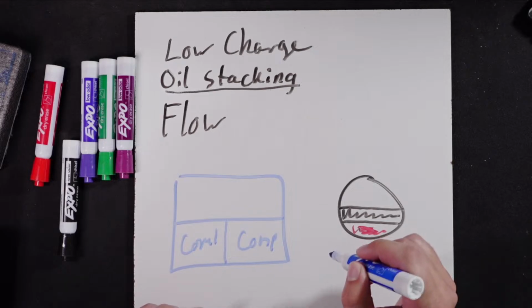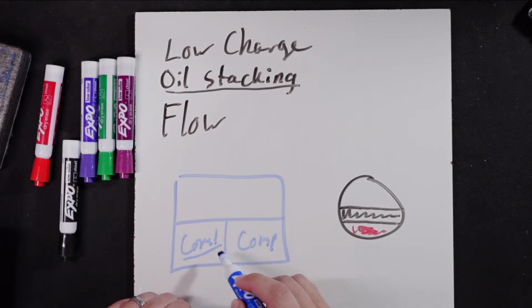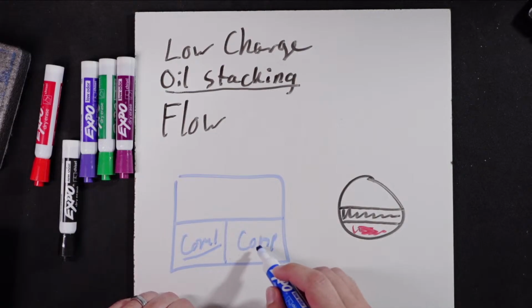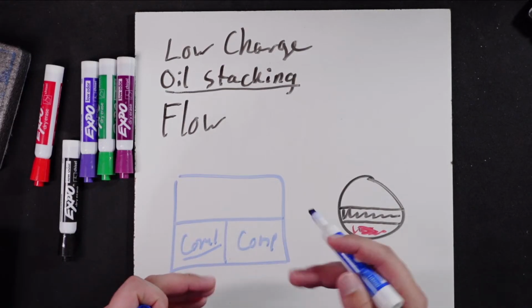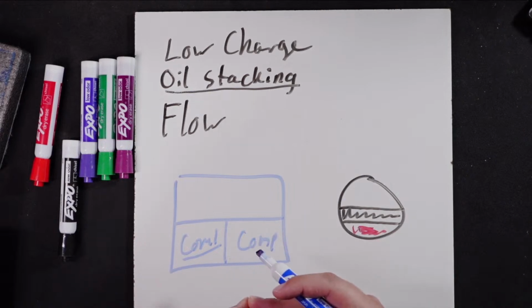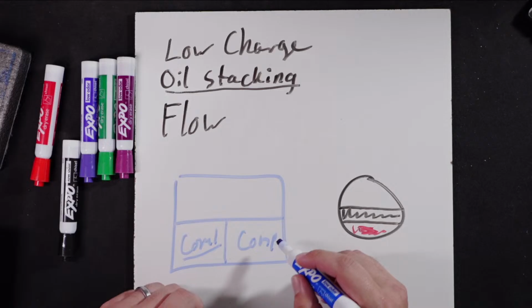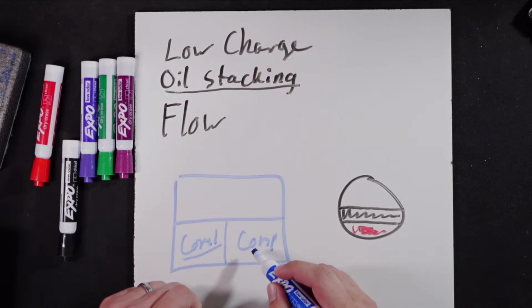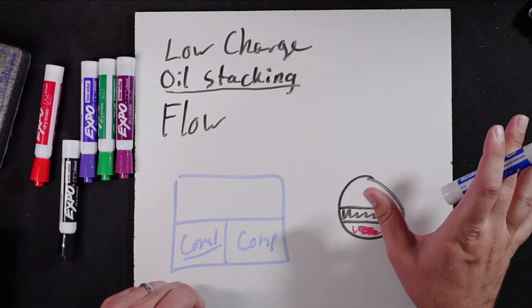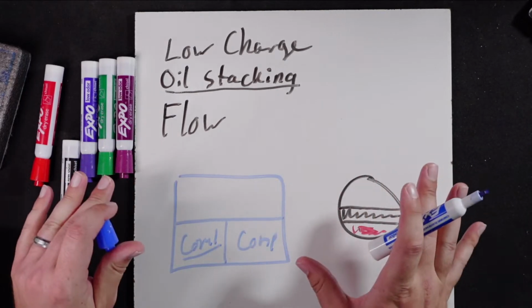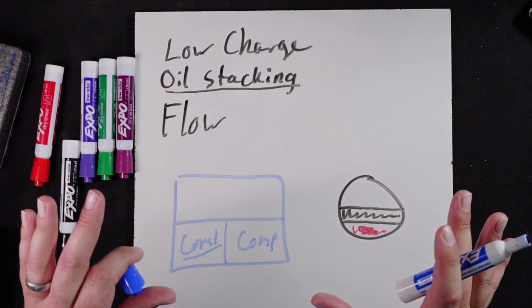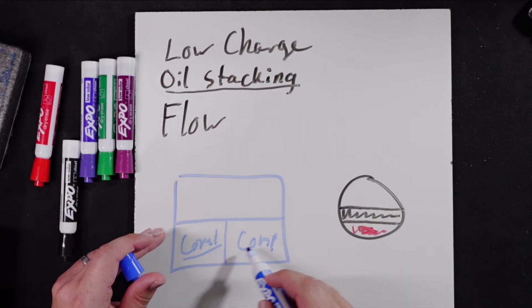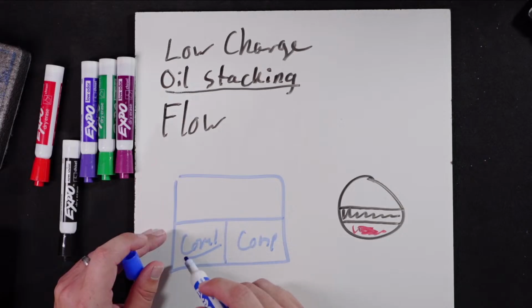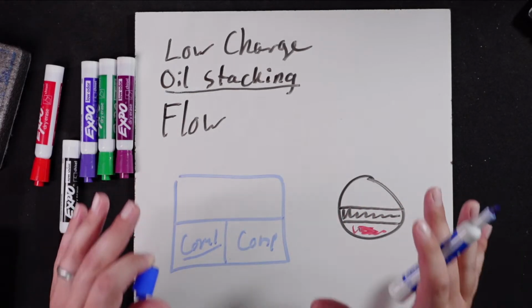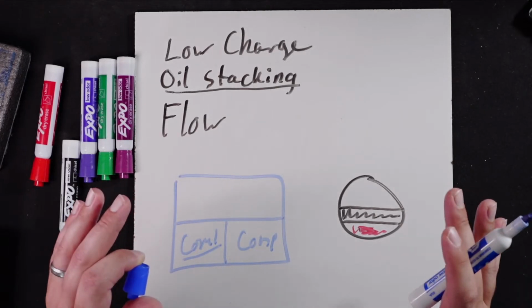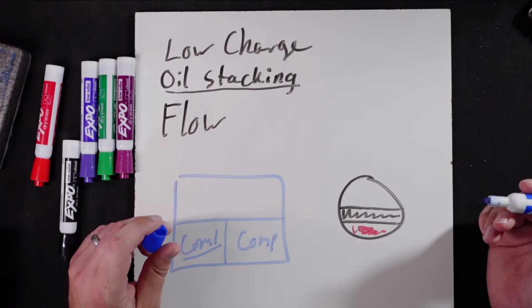So in some scenarios, a problem on 1 can cause some weird conditions on 2 that would make you think they're correlated. That's the word I'm looking for. Because they share the same drive, and compressor 2 can't run independent of compressor 1 on the speed aspect. So be careful of that process. We don't want to get in a spot where we think it's both circuits, but it's really one. Now, I would assume in this case you're actually seeing the alarm on both circuits.